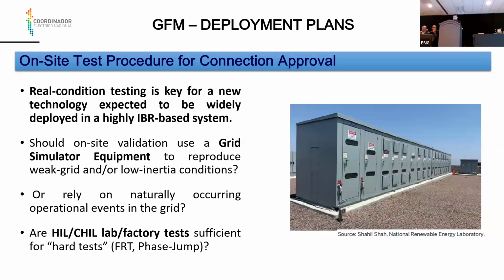Another question for discussion is, are hardware in the loop, control in the loop, laboratory or factory tests sufficient for hard tests in a specific system like the Chilean system? We currently don't have any certification process for inverters in Chile, or for grid forming inverters or systems. So this is an issue for us. It is something like an irony that we have certification for, I don't know, refrigerators, iron machines, but not for grid forming technology.